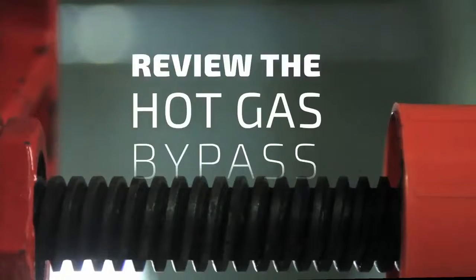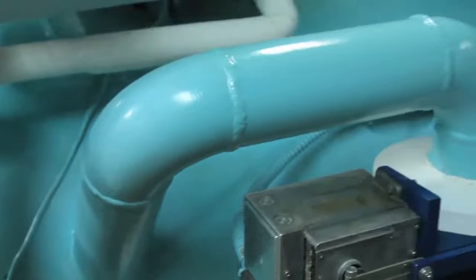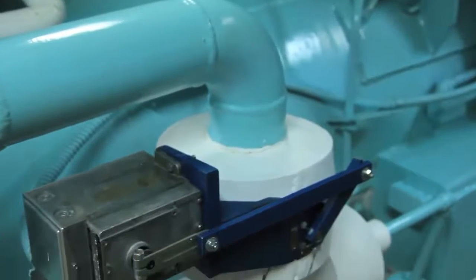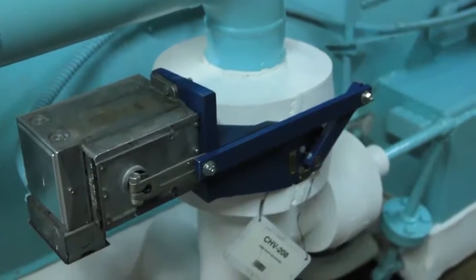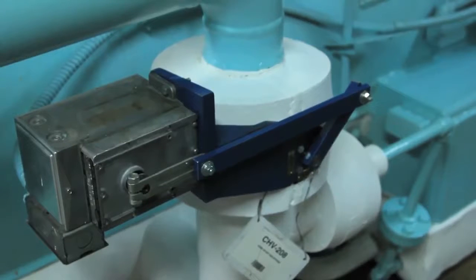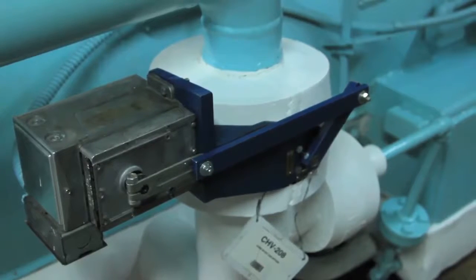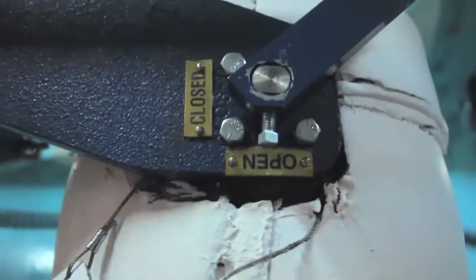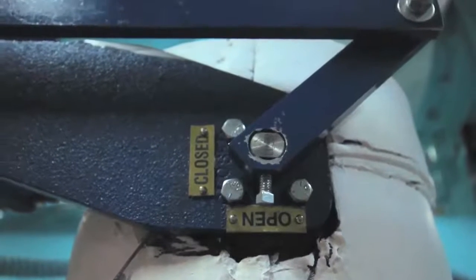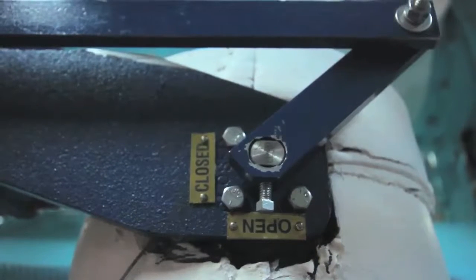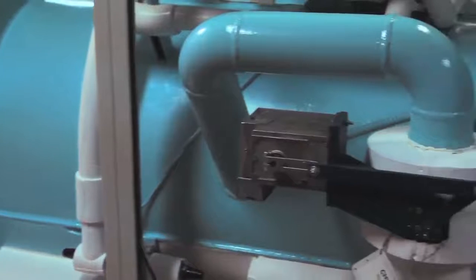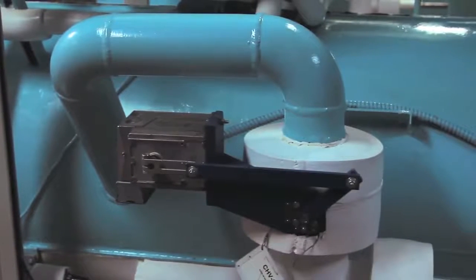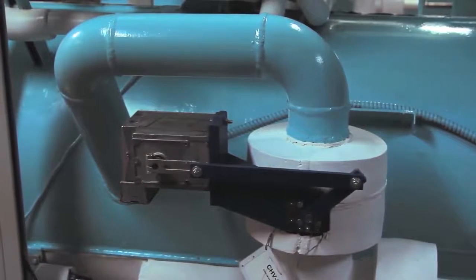Let's review how the hot gas bypass system works. The entrance side is tied to the condenser inlet section where you have a higher gas pressure. A butterfly valve, this is not really a metering device, we are working with the gas at this point, not a liquid, controls the flow back into the cooler. This artificially raises the cooler pressure, preventing unnecessary cycling.